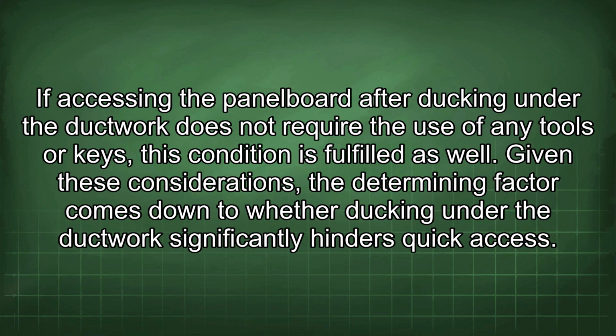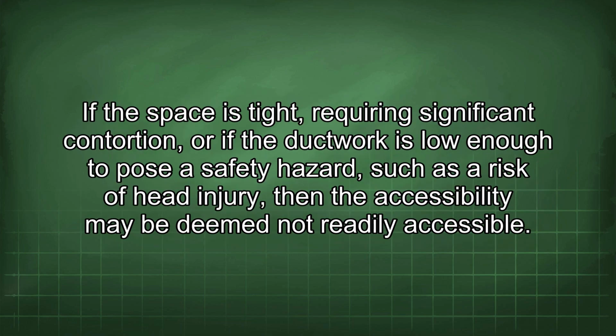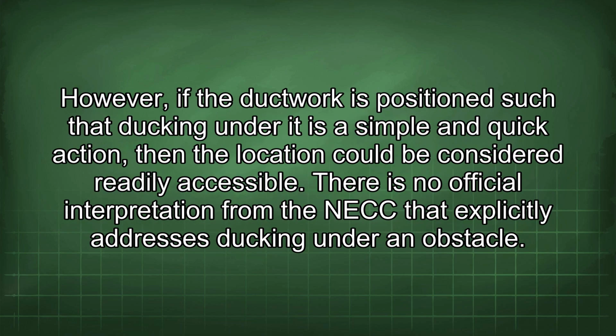Given these considerations, the determining factor comes down to whether ducking under the ductwork significantly hinders quick access. If the space is tight, requiring significant contortion, or if the ductwork is low enough to pose a safety hazard, such as a risk of head injury, then the accessibility may be deemed not readily accessible. However, if the ductwork is positioned such that ducking under it is a simple and quick action, then the location could be considered readily accessible.